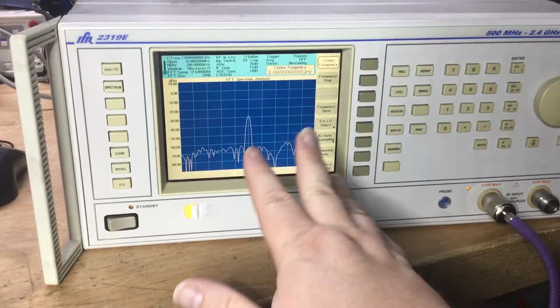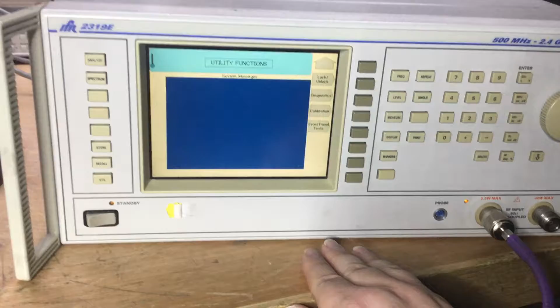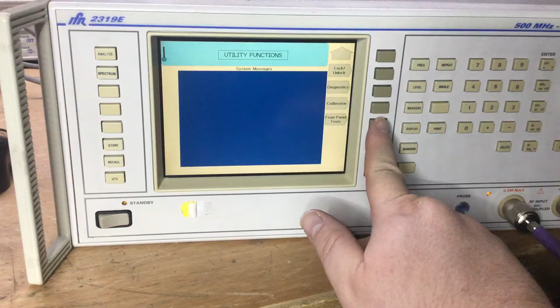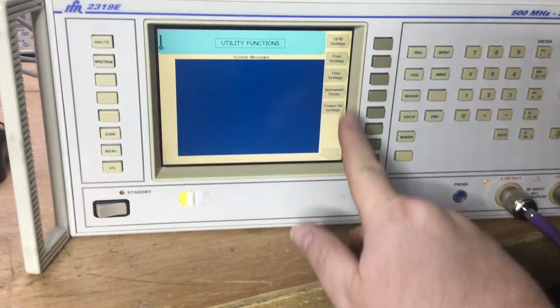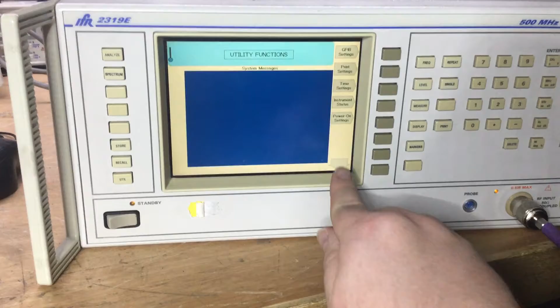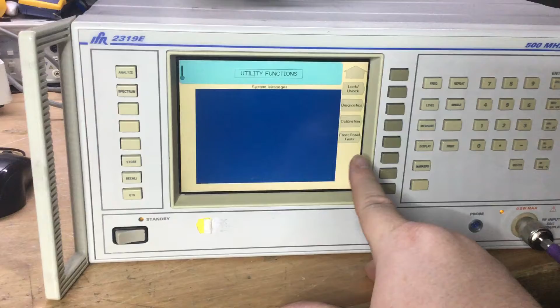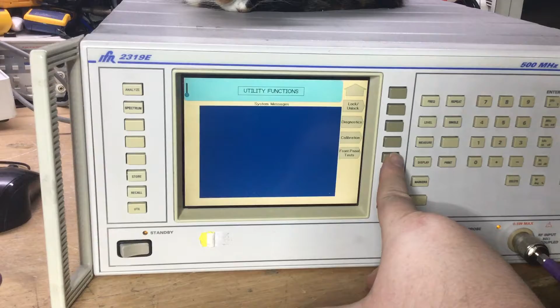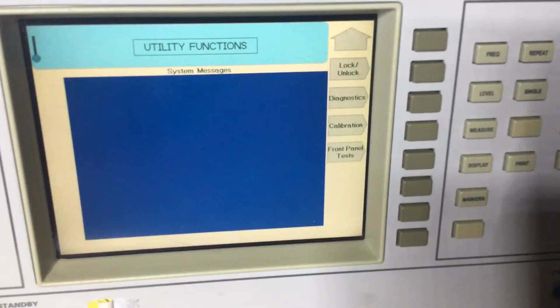Okay, so talk about can't see the wood for the trees. I found out where we need to go from the spectrum display here. We go to utils, and what I couldn't see is when we go to, where is it now? That was it. I was in this menu before, talked about things like power on settings and things like that. Well, this little arrow here, I just missed that. So if you press that, then you get this menu here, and the diagnostics, there's calibration and factory, whatever that is. Can't see it through the camera. What does that say? Oh yeah, front panel tests, calibration, diagnostics.